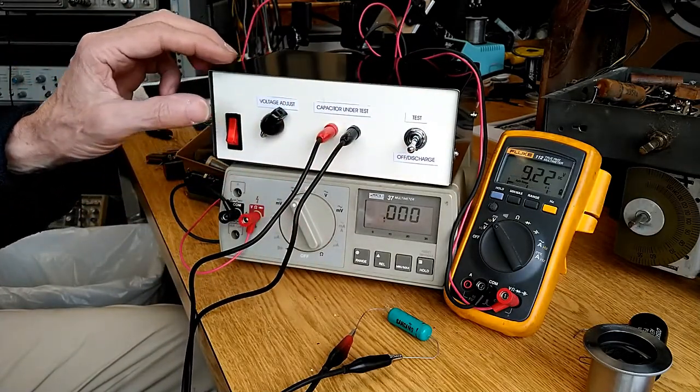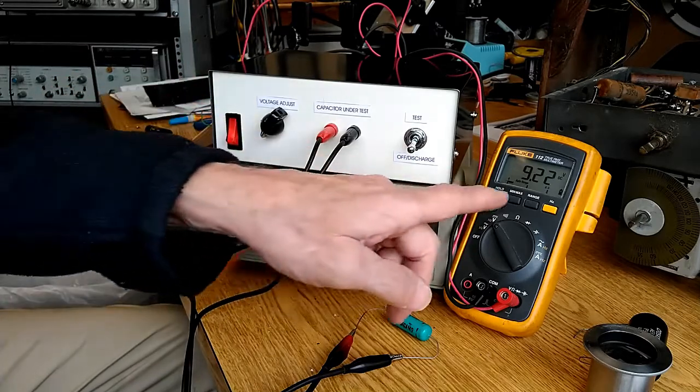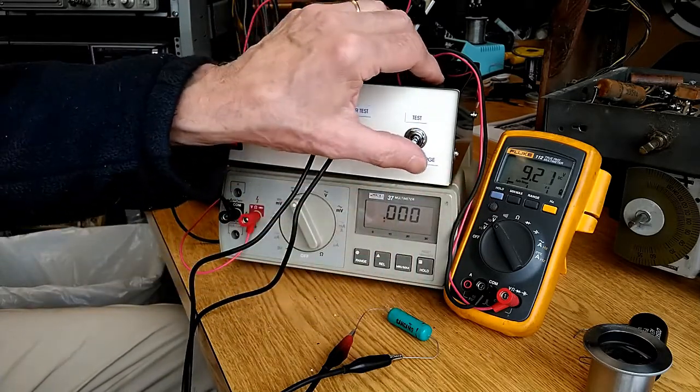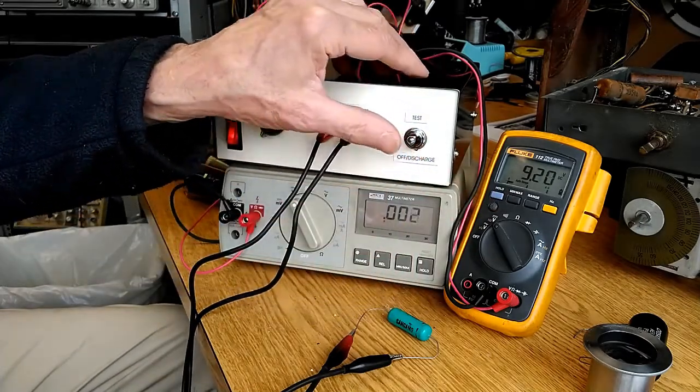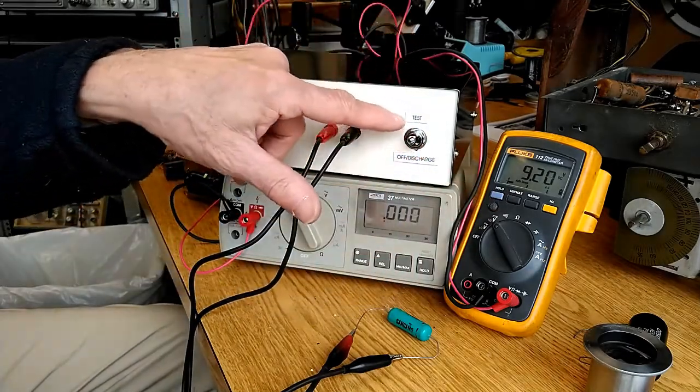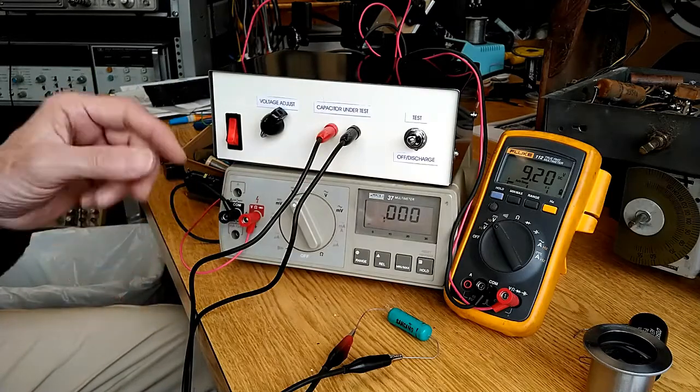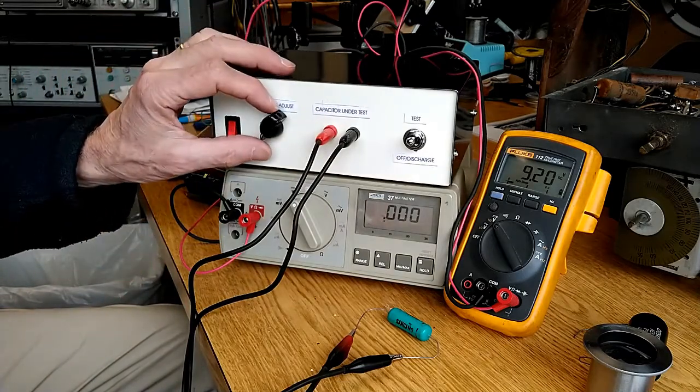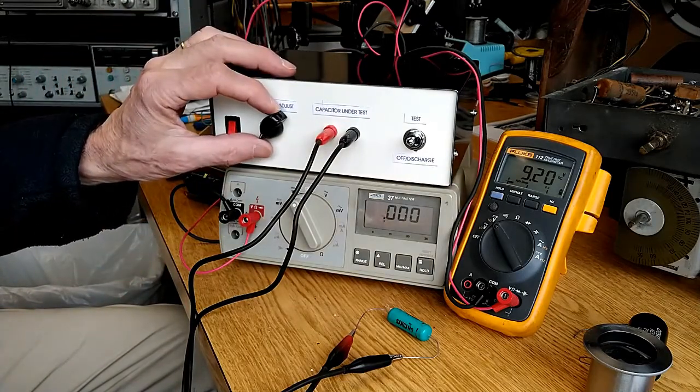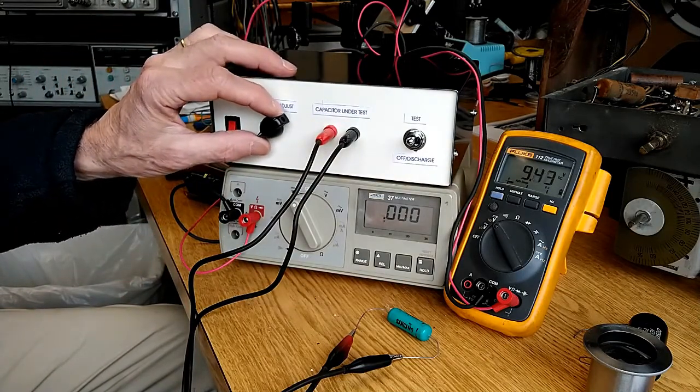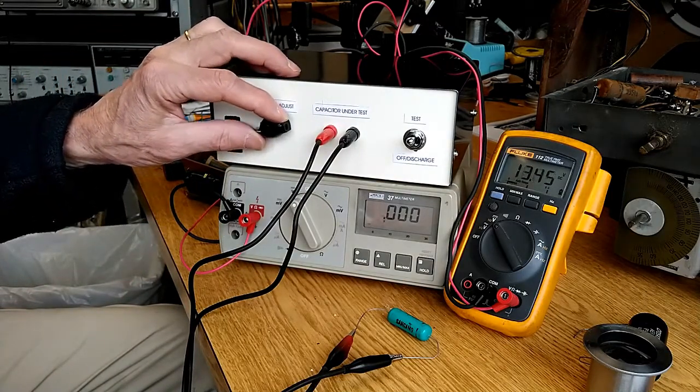Turn the unit on. We can see that initially there's nine volts across the capacitor. I'll put it in test position and we'll increase the voltage up to the rated voltage of the capacitor.